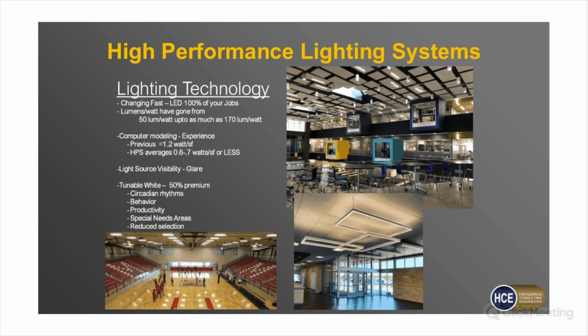So it's really made computer modeling of the lighting layouts, spacings, and heights prevalent—the lumens, the watts, all of that has to be modeled more frequently now. Used to be, for years, you had a 3-lamp T8 2x4 fixture, and you knew if you used it on an 8x8 spacing, you got a certain number of foot candles for a 9-foot ceiling. If you used 10x10 spacing, you knew you got this many foot candles on the desk.